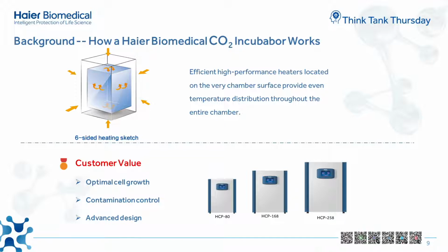First of all, let's present how a Haier Biomedical incubator works and how customers choose the right CO2 incubator. Water jacket and air jacket CO2 incubators are the most common types of cell tissue growth chambers used in laboratories. Water jacket incubators rely on heated water within the chamber walls to maintain a uniform temperature throughout the incubator. Due to the high heat capacity of water, they are capable of maintaining the desired temperature for a long duration.